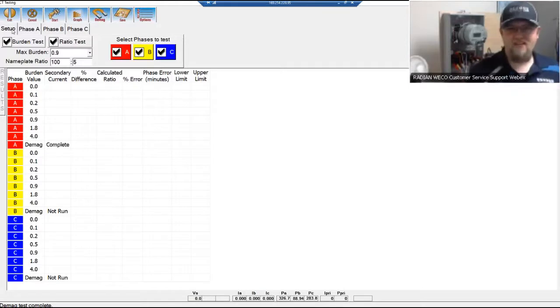So once you've added in your serial numbers, model numbers, and accuracy classes for all three phases, and you've got your test set up like I have in this case, I want to do my burden test at 0.9 ohms and my ratio test of 100 to 5 CT on all three phases. Good to go.